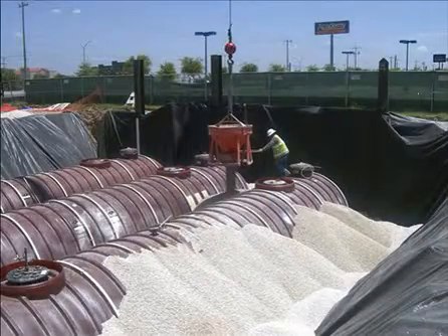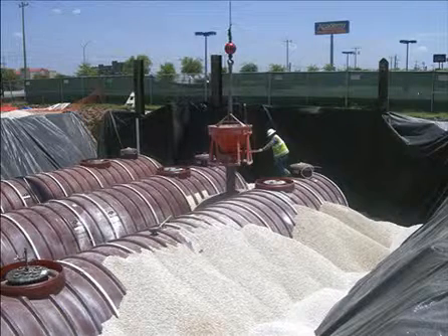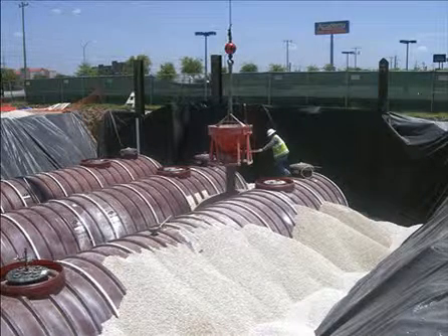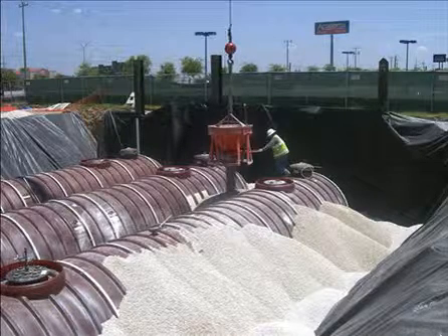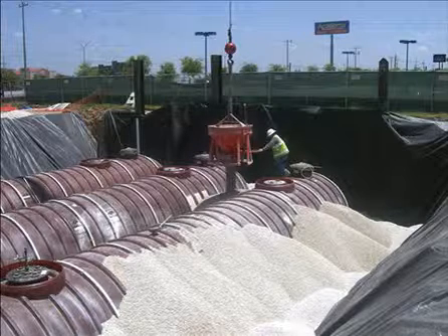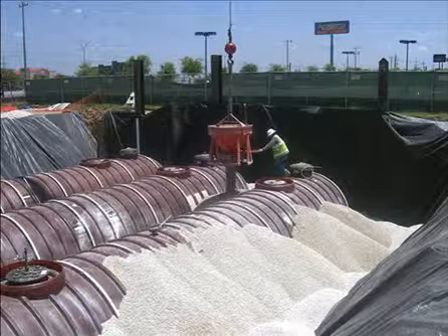Design coordination issues for underground tanks include civil, geotechnical, structural, and electrical issues. Here is a list of some of the most common issues: access to the tank location for delivery vehicles, geotechnical issues that increase installation costs, underground utility interferences, structural or foundation zone of influence issues, building wall details for piping penetrations, and conduit or wiring definition for monitoring and control.